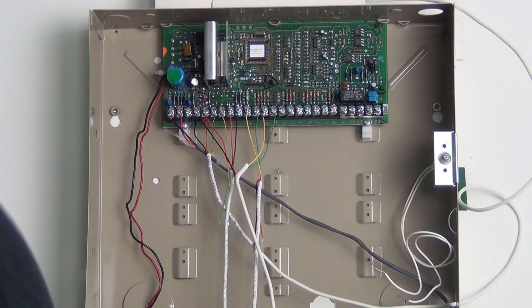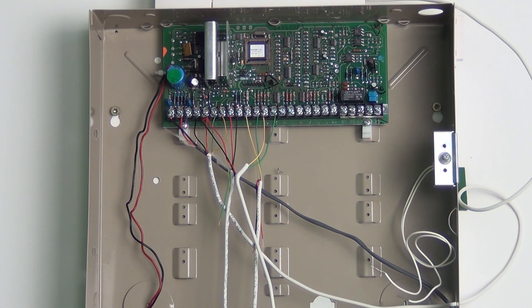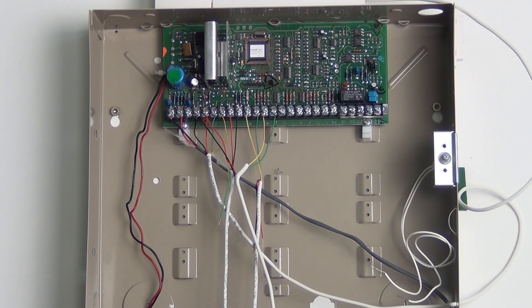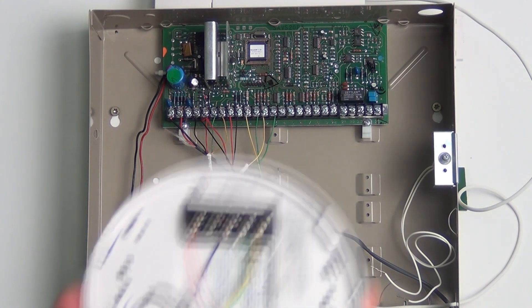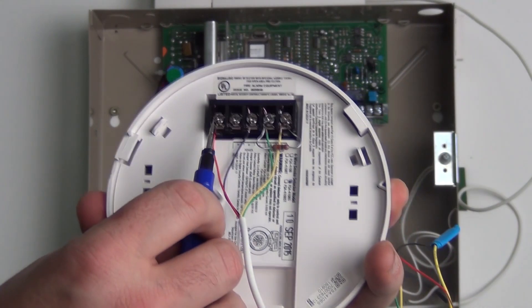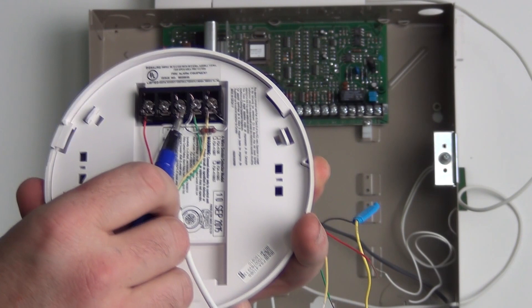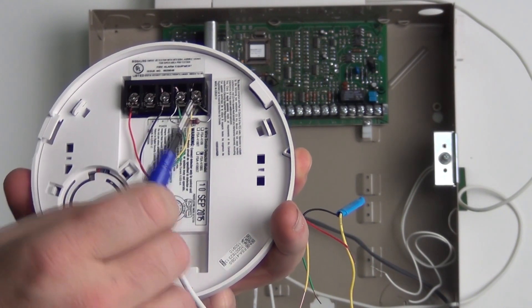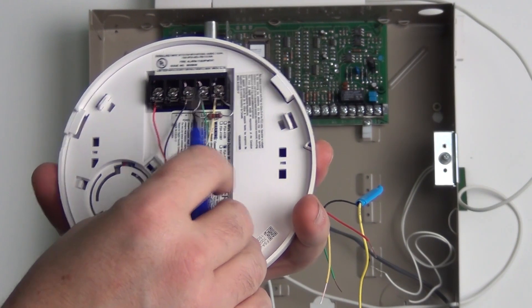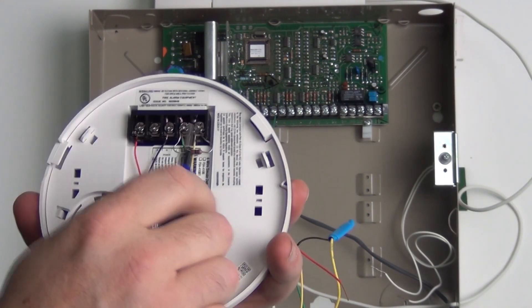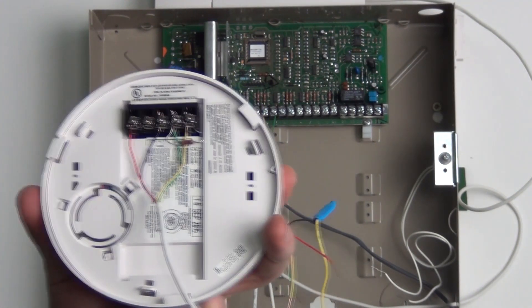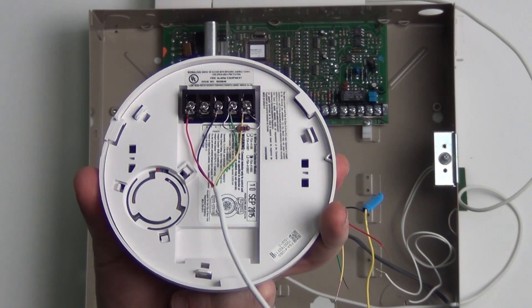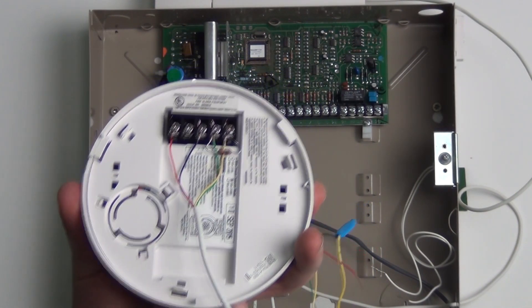The last one we are going to do is a 4-wire smoke. Now the 4-wire smokes, you can take these and zone them out on their own individual zones, but to do a reset for these smokes you will have to do a little bit of special wiring. As you can see from the 4-wire smoke I have here, I have it wired with the red wire on the first positive terminal and the black wire on the negative terminal. Then I have my normally open and common terminals here with the green and yellow wires. I have taken a resistor and run it in parallel between the 2 posts here. Since it is a normally open device, the resistor will be in parallel between the 2 posts.